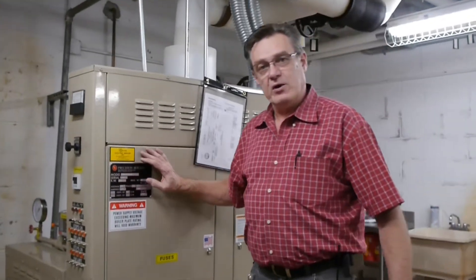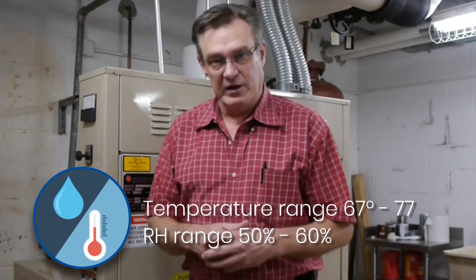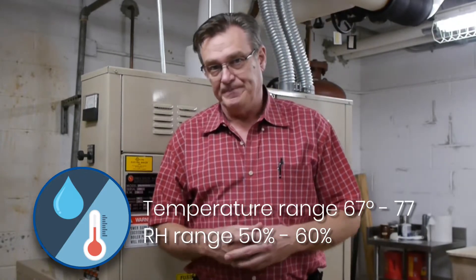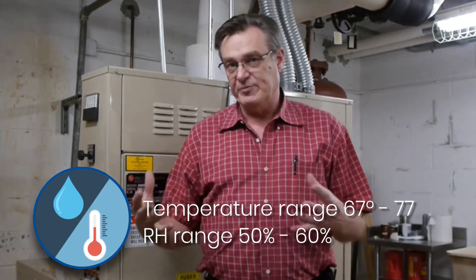Our steam boiler right here works predominantly in the wintertime when it's cold. The steam system is not for heat. The steam system is to put humidity back in the air. Part of the environment of maintaining our art collection and so forth here is temperature and humidity. We try and maintain a specific range based on where we're located. The steam boiler is a crucial part of that.